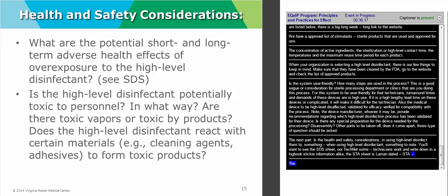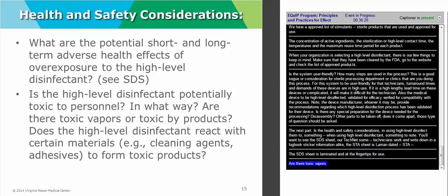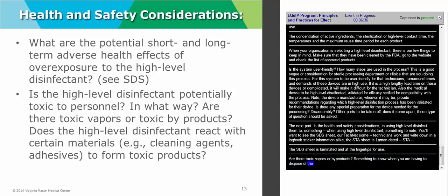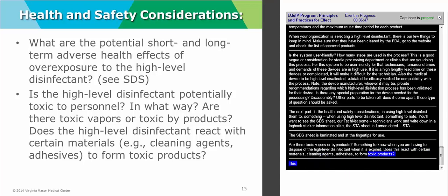Is the high-level disinfectant potentially toxic to personnel? If it is, in what way? And are there toxic vapors or toxic byproducts? Something to note when you have to dispose of that high-level disinfectant when it becomes expired. Also, does the high-level disinfectant react with certain materials, like cleaning agents or adhesives, to form toxic products? Those are definitely questions that you could present to the manufacturer when considering a product for purchase or use.